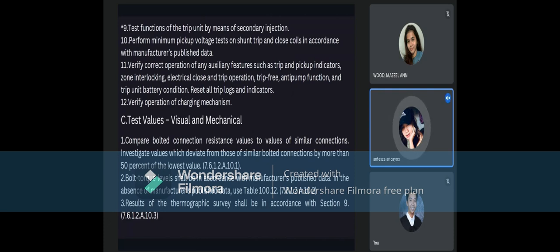Let's talk about the test values of the visual and mechanical inspection. The first is compare bolted connection resistance values to values of similar connections. Investigate values which deviate from those of similar bolted connections by more than 50% of the lowest value, which is in section 7.6.1.2.A.10.1. Second is bolt torque levels shall be in accordance with manufacturer's published data. In the absence of manufacturer's published data, use table 100.12. The third is the results of the thermographic survey shall be in accordance with section 9.